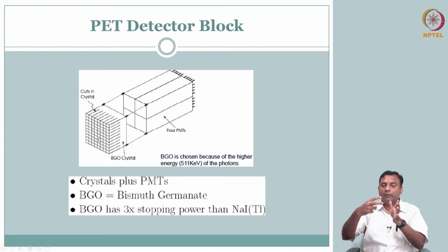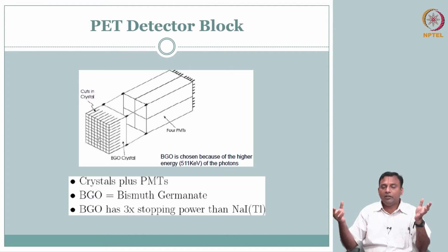You have a crystal and at the back of it you have your photomultiplier tube, and then we will use this idea of x comma y, remember z pulse, so that we can get our x comma y localized by center of mass calculation. So you could use that to your advantage, and therefore this is a nice combination.